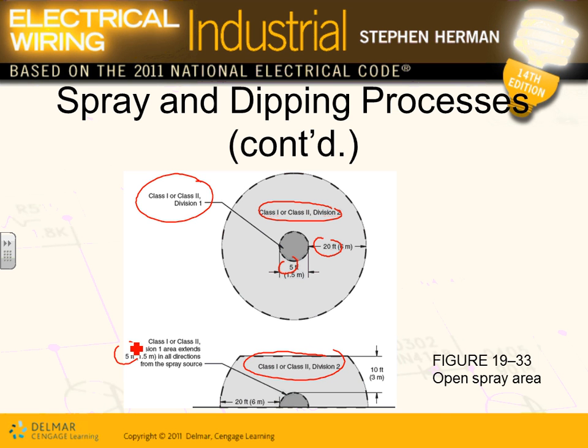So Derek, I know there's a lot of information. If you ever get into places where you have flammable gases, vapor, or dust, flag it. It's a special wiring system, unlike where we're done with here, where you can use EMT, anything you want, any approved method. What's in it for you guys when you do estimating? It's going to be expensive to install the system, maintain the system, and troubleshoot the system. Everything is expensive there.